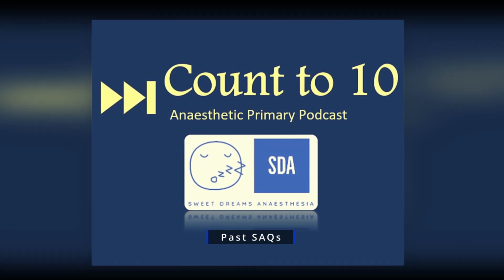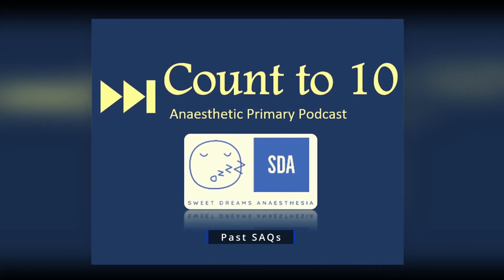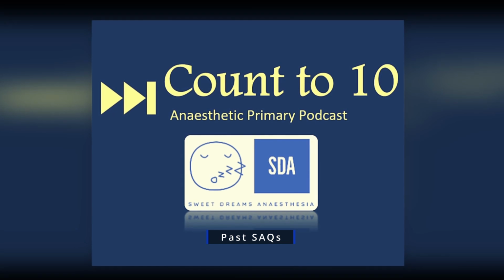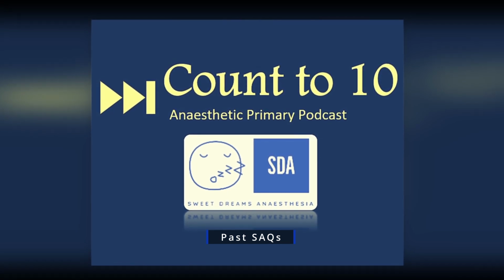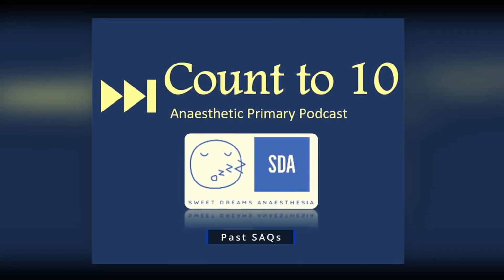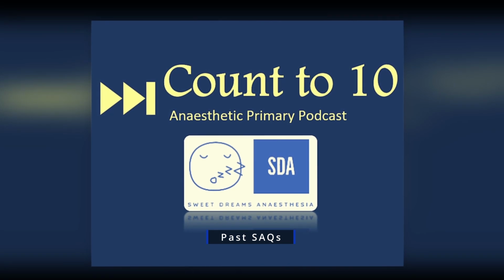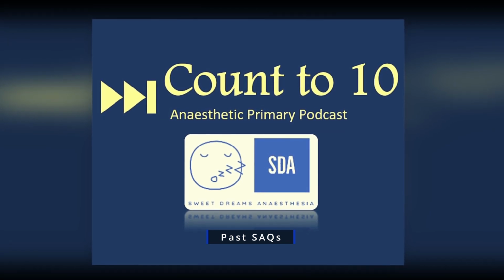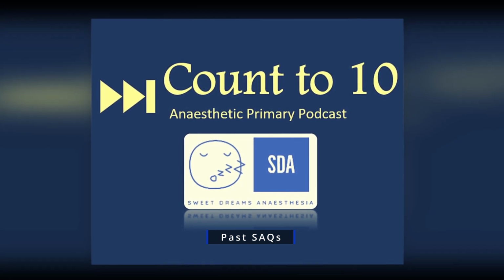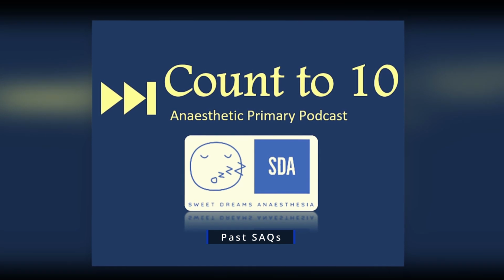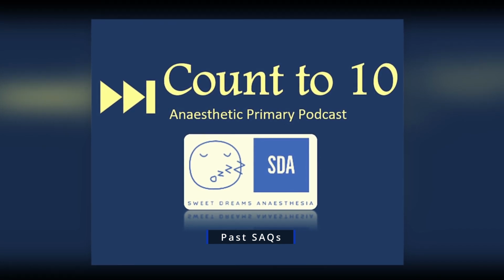Systolic blood pressure correlates to when the rise in the rate of amplitude is at its highest. Mean arterial blood pressure correlates to when we reach maximum amplitude. And diastolic blood pressure can be measured using several techniques that we've discussed previously. The easiest one to remember is when there's the maximum rate of decrease of amplitude.